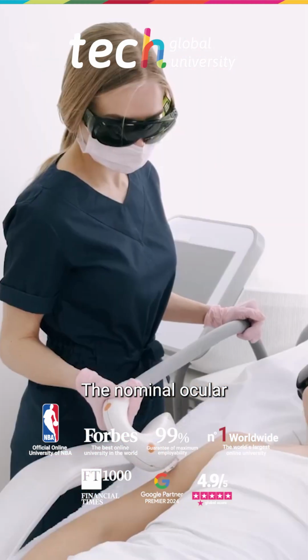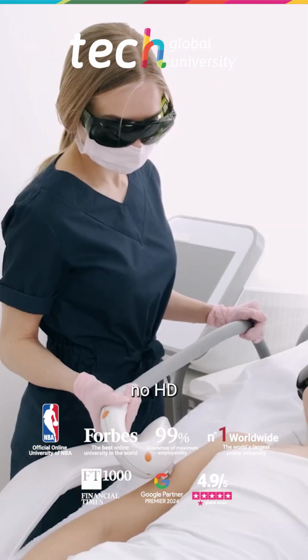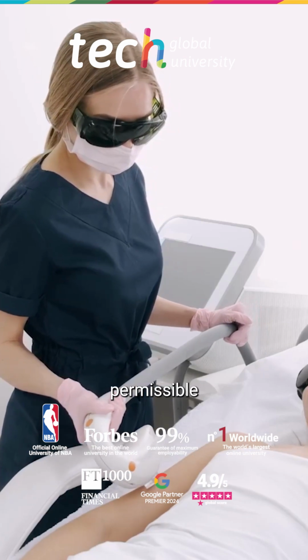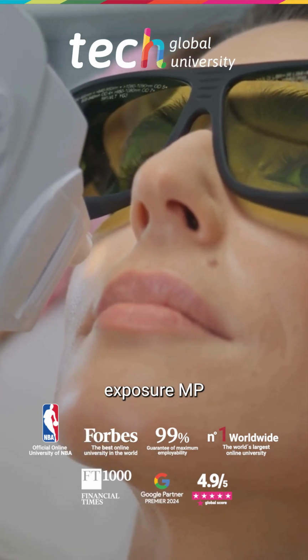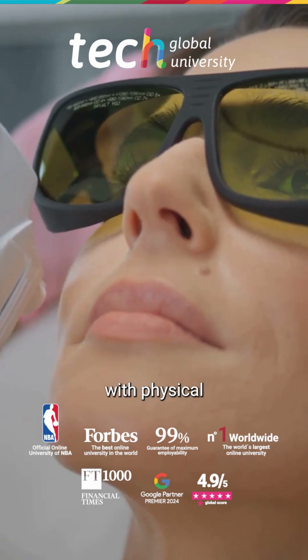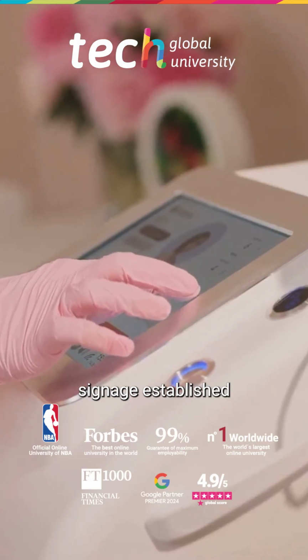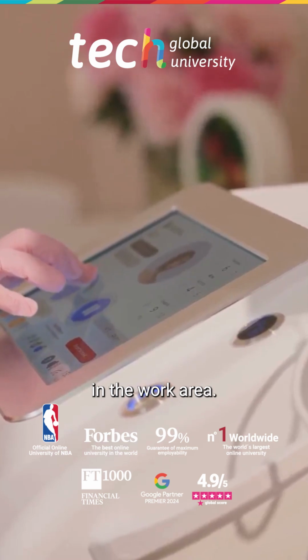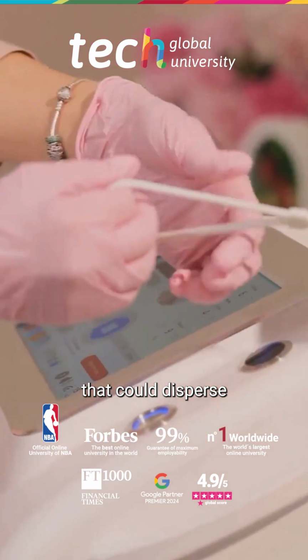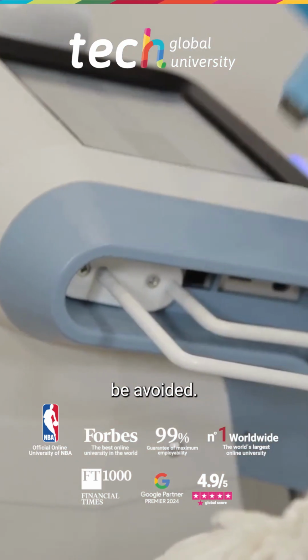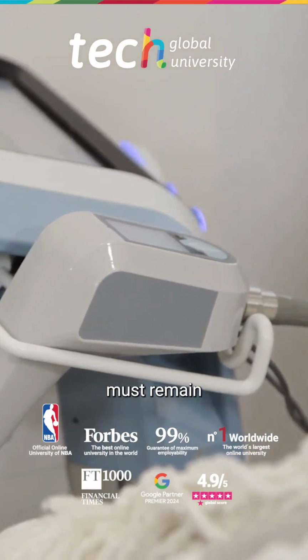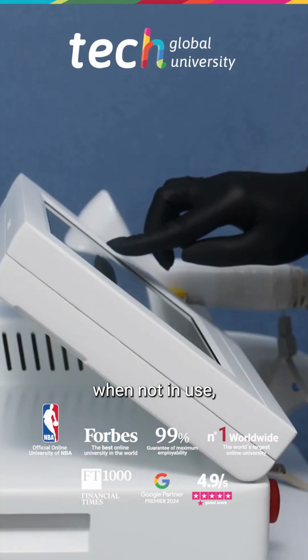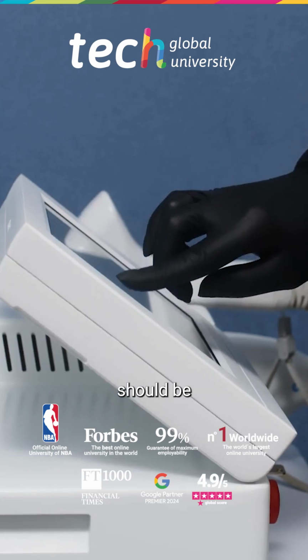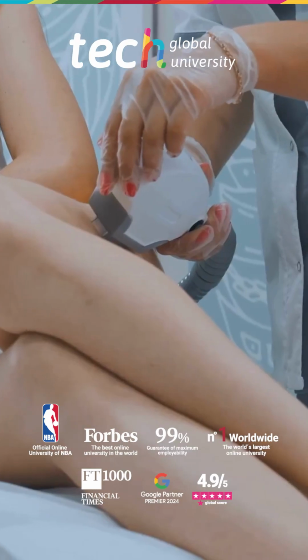The nominal ocular hazard distance, NOHD, and the maximum permissible exposure, MPE, must be identified, with physical barriers or clear signage established in the work area. Reflective surfaces that could disperse the laser beam should also be avoided. The laser must remain in standby mode when not in use, and smoke evacuators should be employed in ablative procedures.